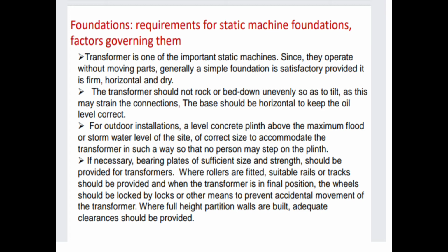The transformer should not rock or bed-down unevenly so as to tilt, as this may strain the connections. The base should be horizontal to keep the oil level correct. So this is all about the foundations.